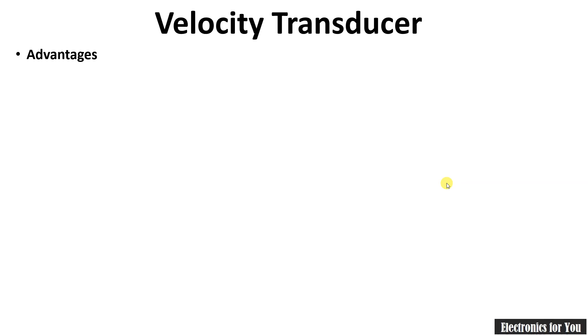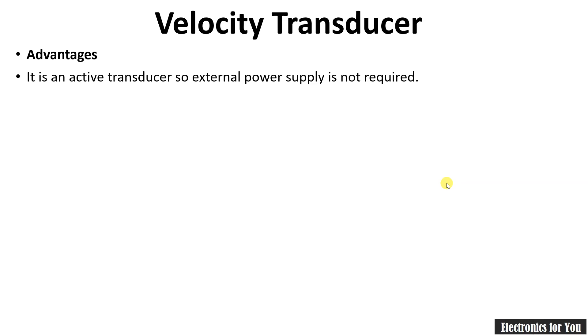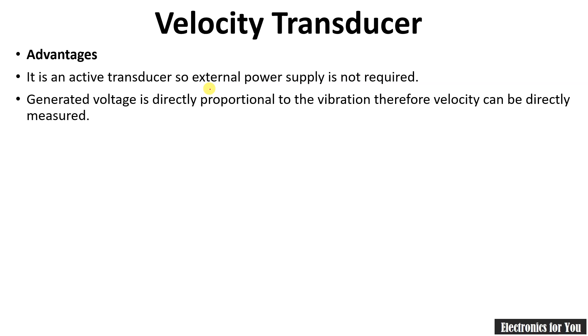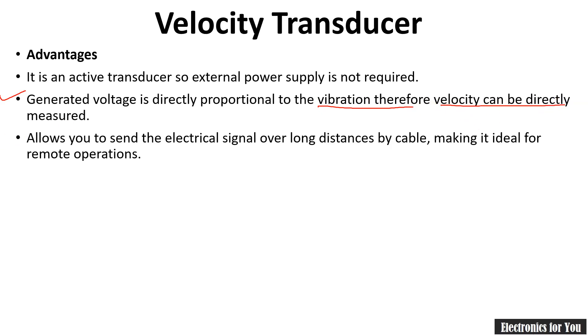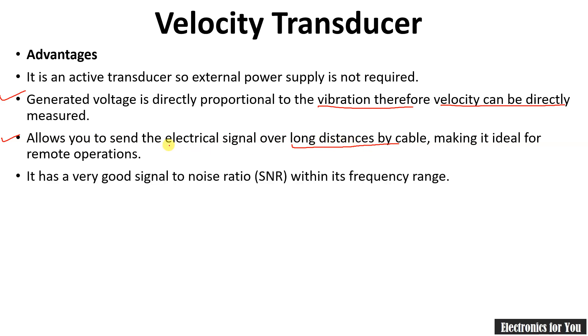The advantages of the velocity transducer: it is an active transducer, so no external power supply is required. The generated voltage is directly proportional to the vibration, so velocity can be directly measured. This transducer allows you to send electrical signals over long distances by cable, making it ideal for remote operations. The velocity transducer also has a very good signal-to-noise ratio within its frequency range.